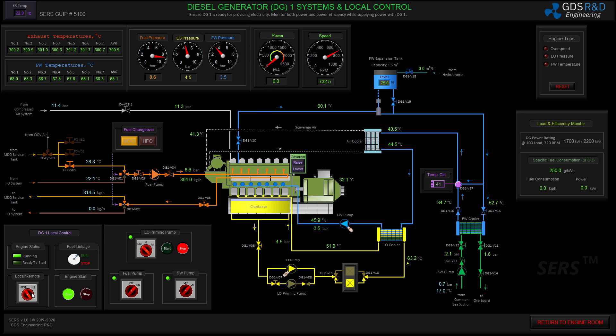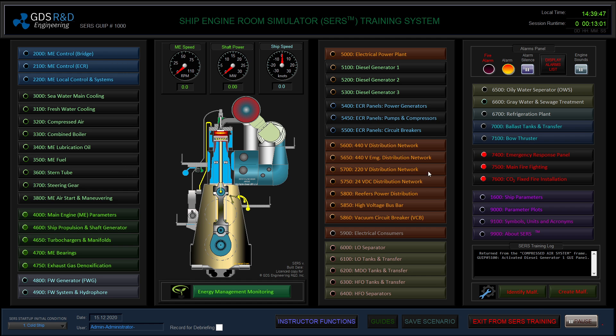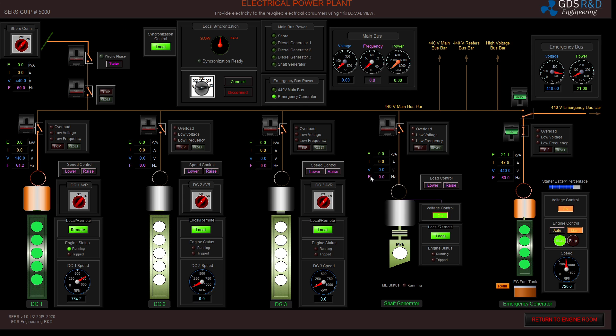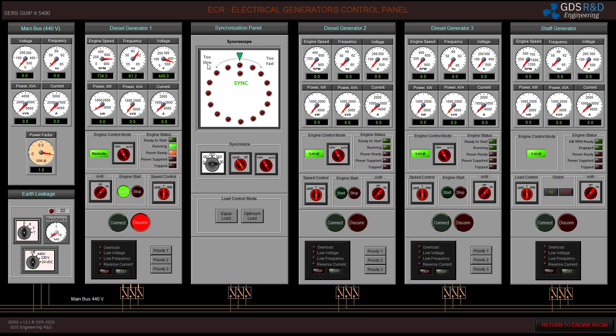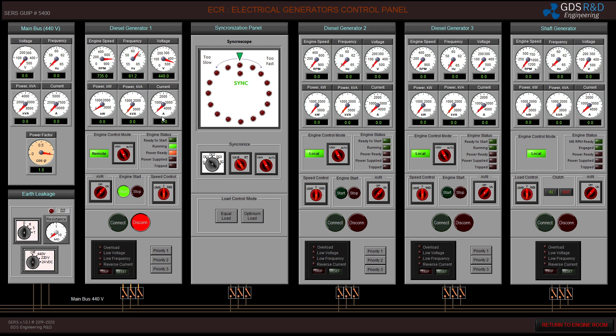I will switch the control to remote position to connect my diesel generator to the bus bar. I will do that in this synchronizer panel. I will switch the synchronizer control to diesel generator one. As you can see, diesel generator number one is at about 61.2 Hz, and I have to adjust that to a stable 60 Hz. I'm going to lower the engine speed to maintain 60 Hz frequency.